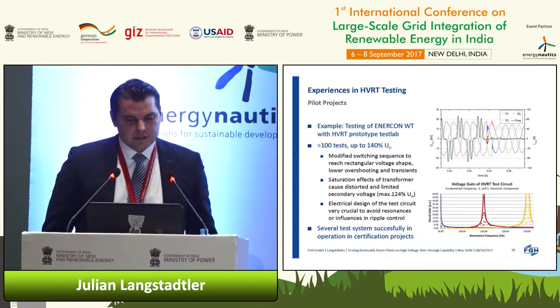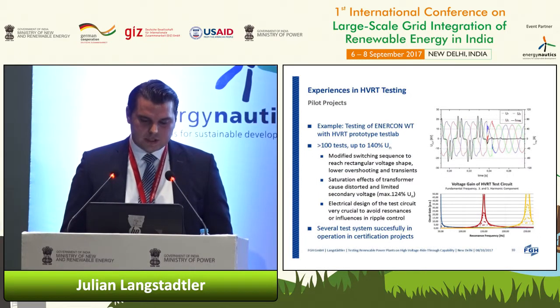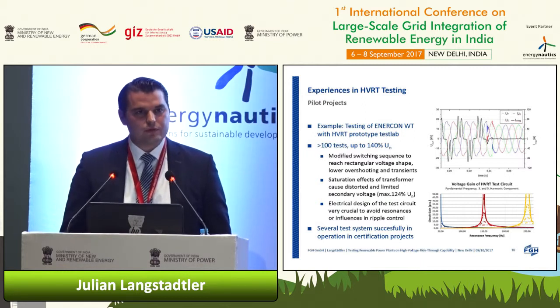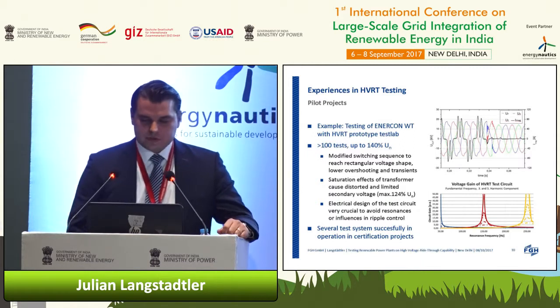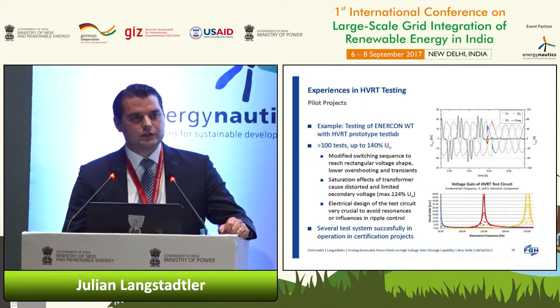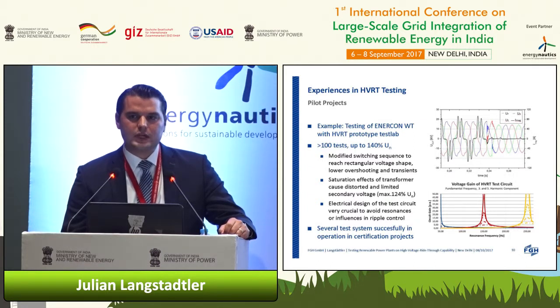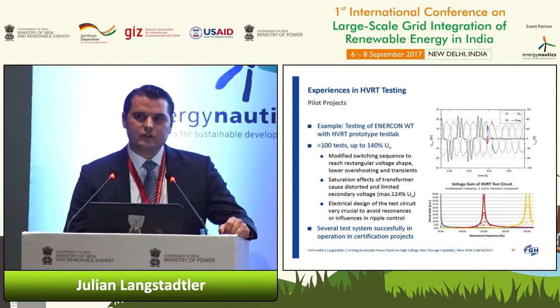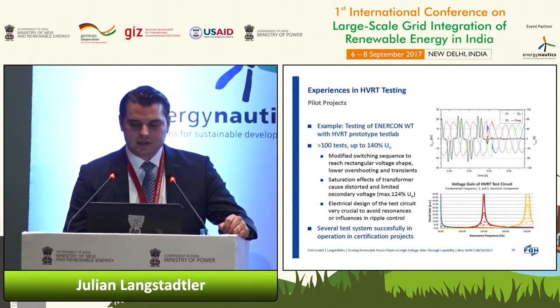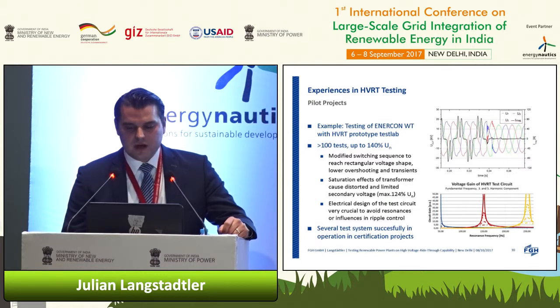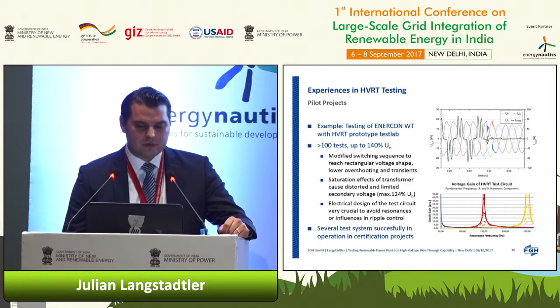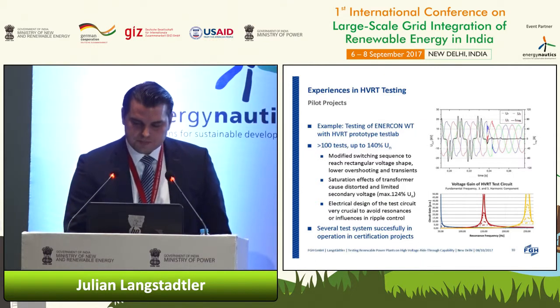From the pilot project testing, we made more than 100 tests, with voltage swells up to 140% of nominal voltage. And we saw some results in the field testing that we had also simulated before. One is that you must make sure you meet the specific ramp rates of the IEC standard. According to the IEC standard, which is currently only a draft version but will be published next year, you have to reach a specific testing voltage level within 20 milliseconds. This is quite fast, and you may have to adapt the switching sequence in order to cope with this requirement.